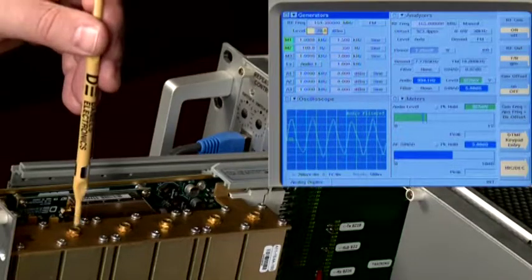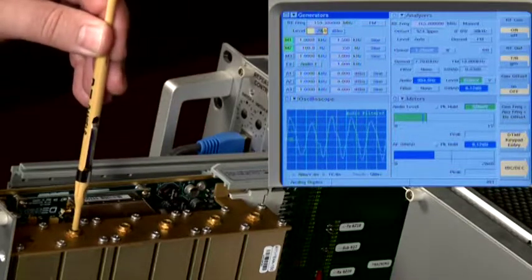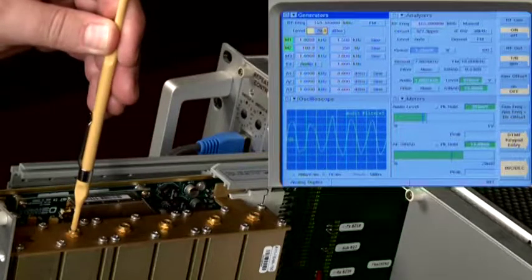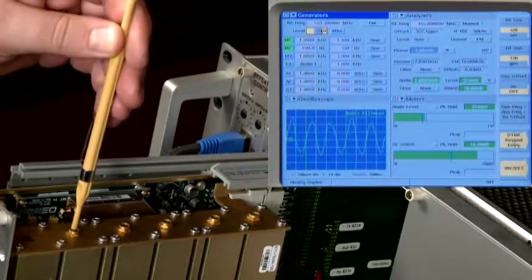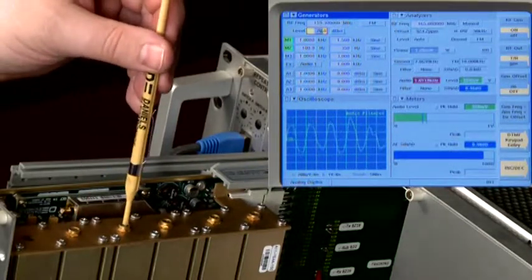Adjust the variable capacitors to tune the RF preselector. Set the signal generator so that noise can be heard on the speaker, then tune the capacitors for the best SINAD measurement. Continue reducing the signal generator level as the capacitors are tuned. There is no specific sequence to tune the capacitors.